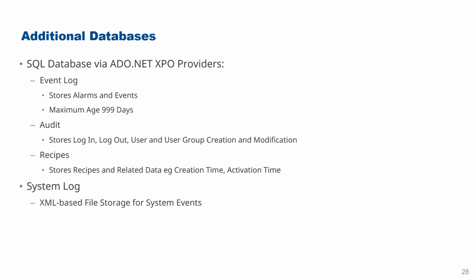First, we have an alarm log, which stores alarms and events. Whenever an alarm occurs, or you configure an event (similar to an alarm but it doesn't appear in the alarm list), it can be stored into the event log. This has a defined format and a maximum age of 999 days, but it lets you store and display all your alarms.